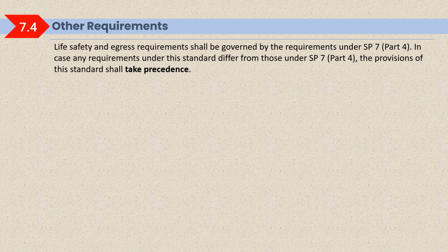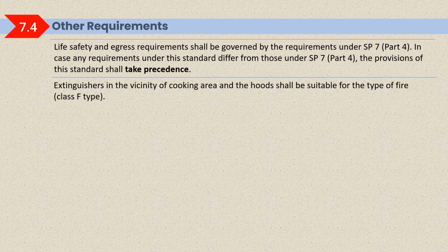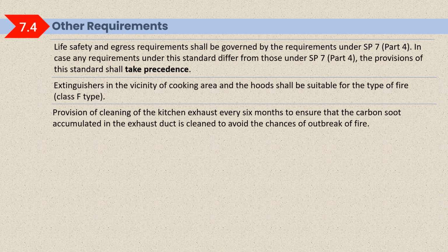In case any requirement under this standard differs from those under SP 7 Part 4, the provisions of this standard shall take precedence. So this standard will take precedence over NBC 2016 if any difference is found between this standard and NBC. Extinguishers in the vicinity of the cooking area and the hood shall be suitable for the type of fire, class F, fat or cooking oil fire. Provision of cleaning of kitchen exhaust every 6 months to ensure that the carbon soot accumulated in the exhaust duct is cleaned to avoid the chances of an outbreak of fire.